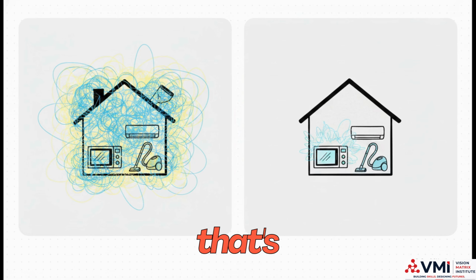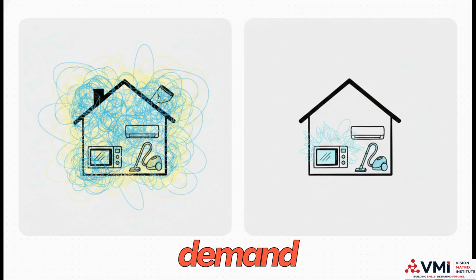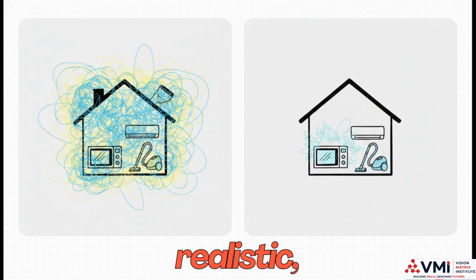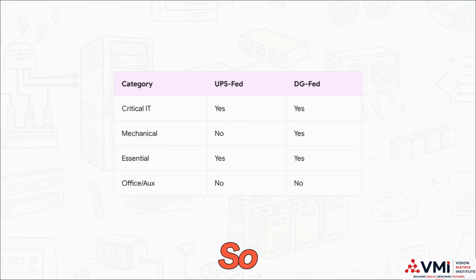No way. And that's exactly why engineers use what's called a demand factor to calculate the realistic real-world usage, or the demand kilowatt. If we actually built the data center for connected kilowatt, it would be insanely oversized and just waste millions of dollars.